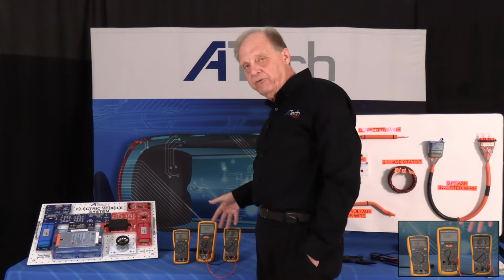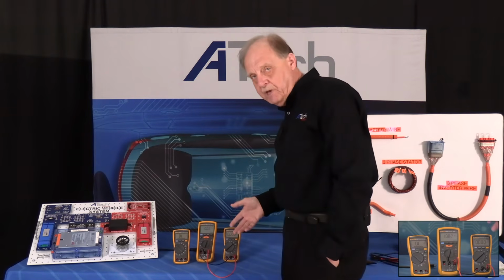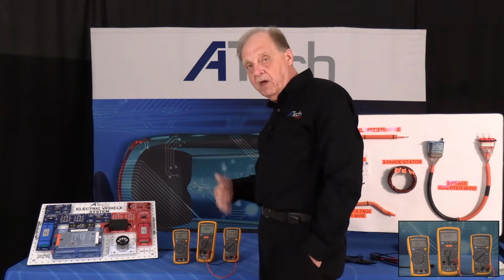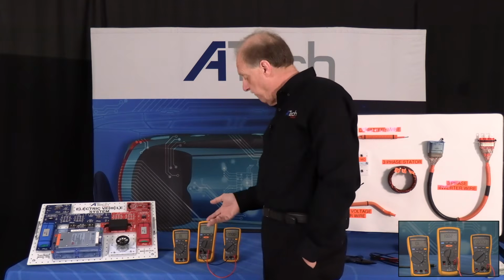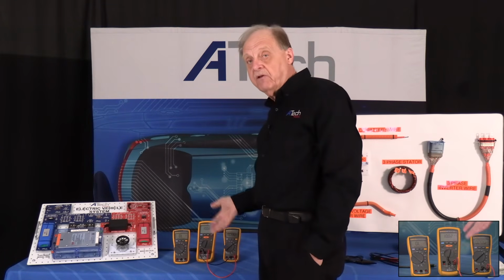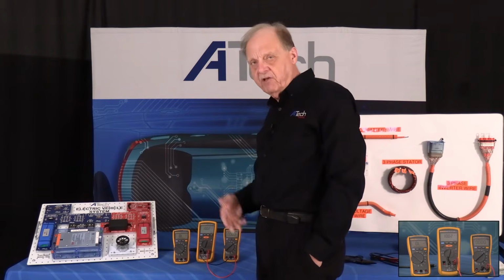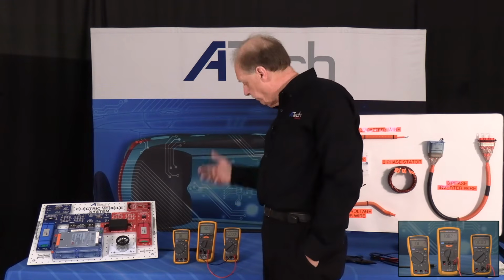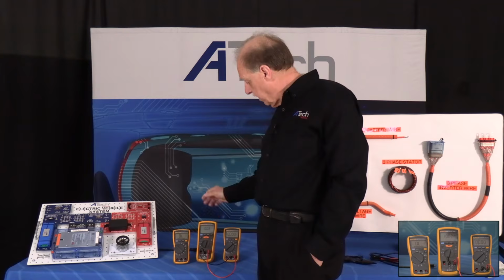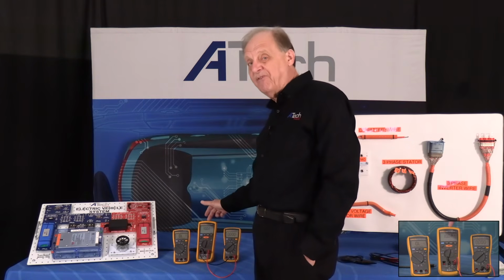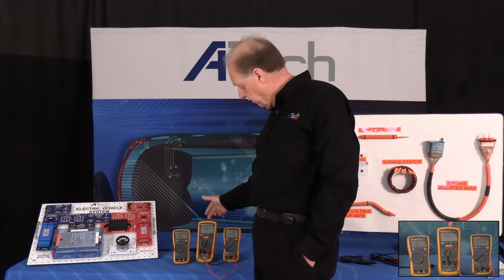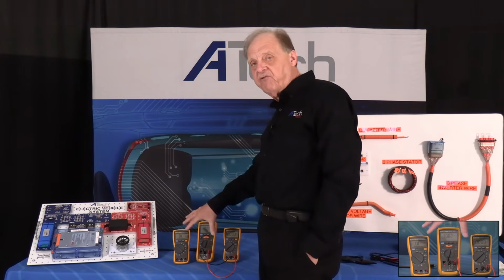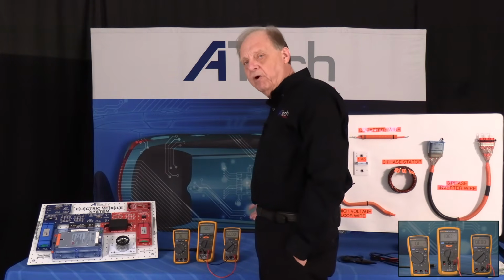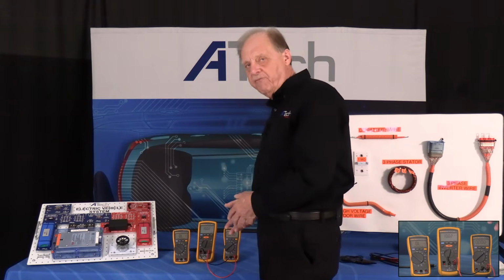This is something you should do with your students, because sometimes they'll buy a meter and it doesn't have the 10 megohms that we need. I've actually had testing show less than 5, and that's going to affect the circuit you're testing. So this is a real quick review of what we look at. This meter is going to put almost 1,000 volts out when it's testing. Something you need to look at. That's why we have to move up to more expensive meters and another level of testing.